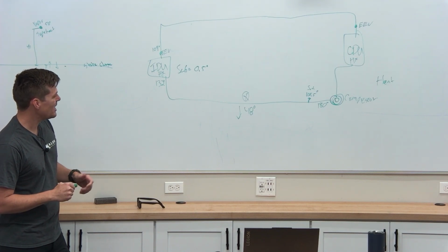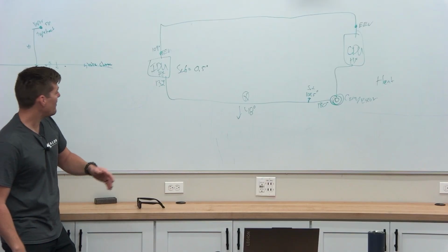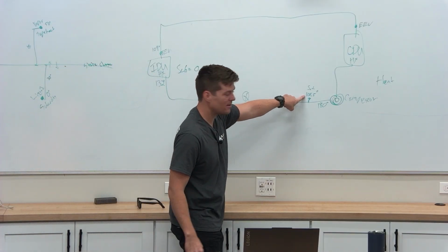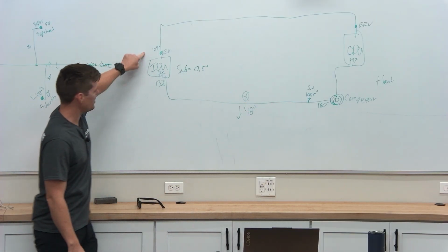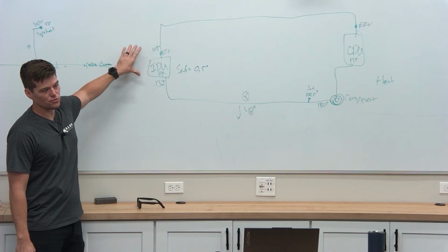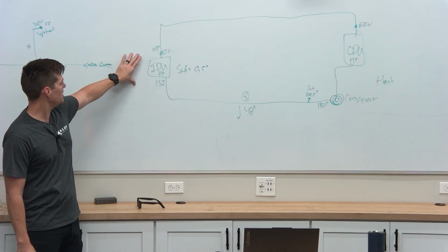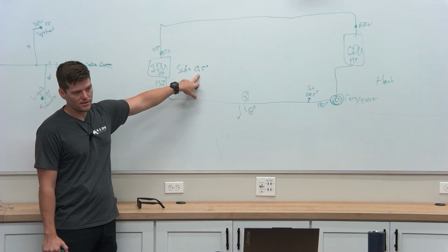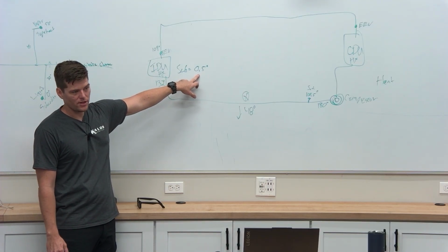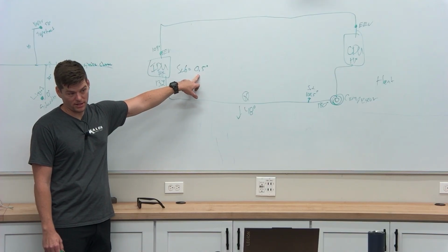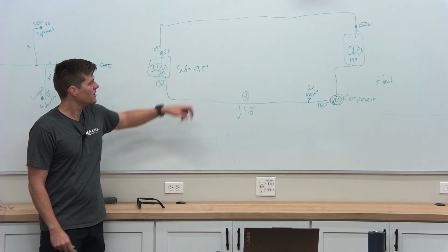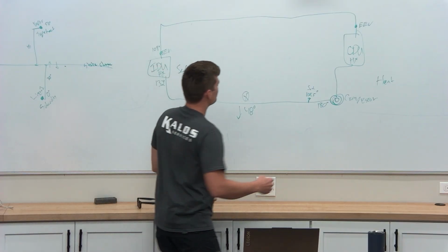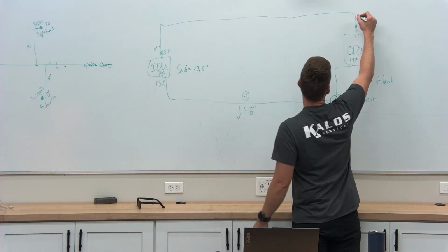Okay? But you can see how, if I don't have this number and I look at this temperature exchange, I think, wow, this thing is really efficient. I'm generating a lot of heat. But here you can see I'm only generating 0.5 subcooling, right? That is a really low quality liquid. It's barely a liquid. So let's keep going. So we make it back to my outdoor unit. What do you think we get to?